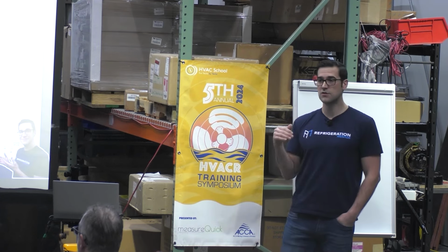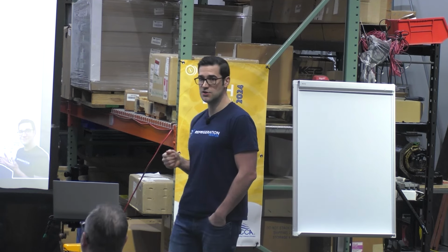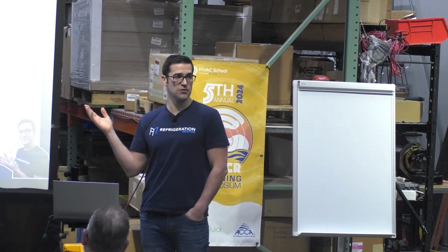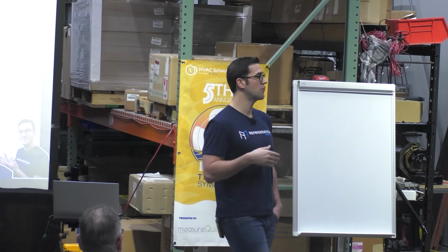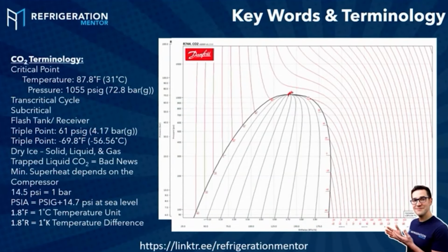When we're above this critical point, there's no pressure-temperature relationship. 410 has a critical point. Above that point, there's no pressure-temperature relationship. So you just can't jump on a PT chart and say, okay, this temperature correlates to this pressure. The other cool thing about being above the critical point with any refrigerant is that it doesn't condense. It's not a liquid, and it's not a vapor. We call it a fluid, a supercritical fluid. And these are different terms that we just need to learn.